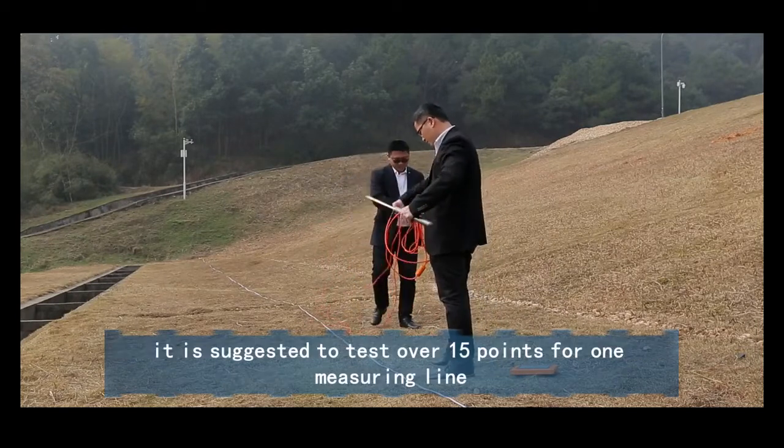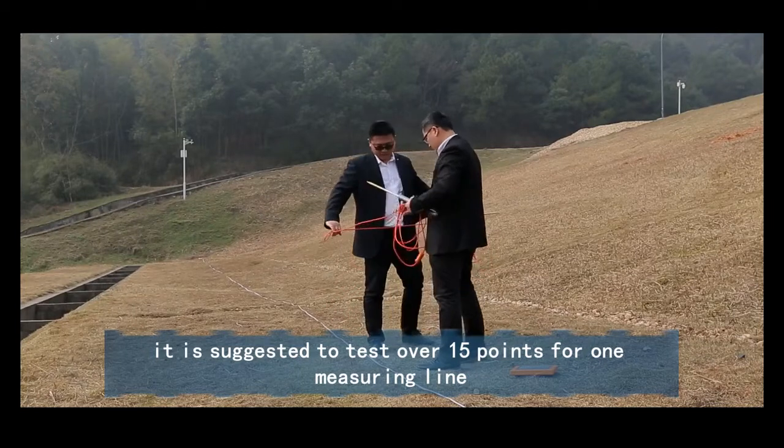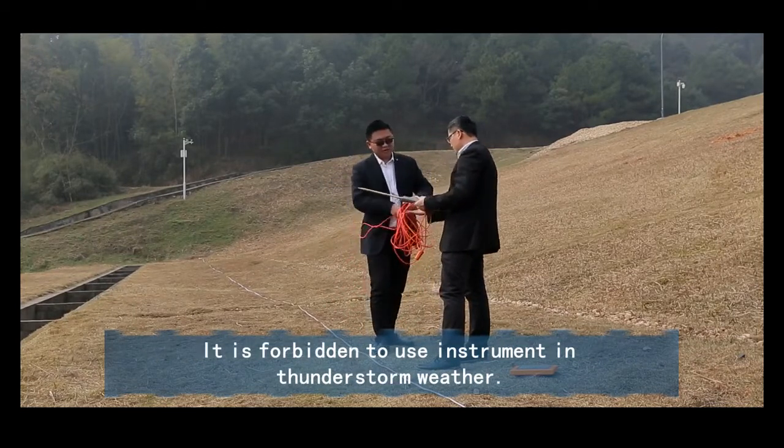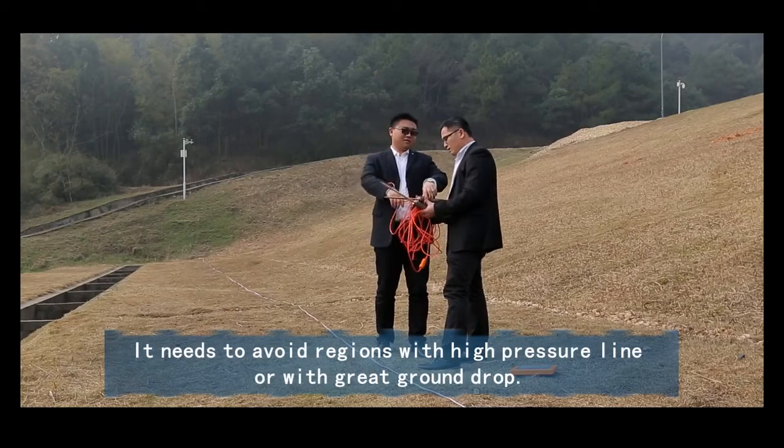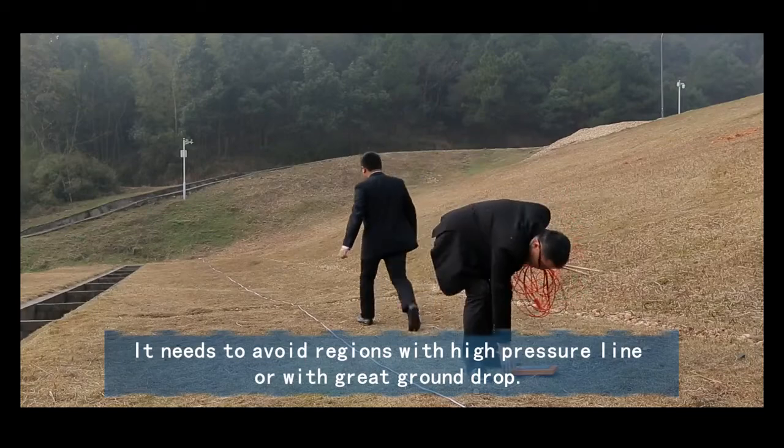It is suggested to test over 15 points for one measuring line. It is forbidden to use instrument in thunderstorm weather. It needs to avoid regions with high pressure line or with great ground drop.